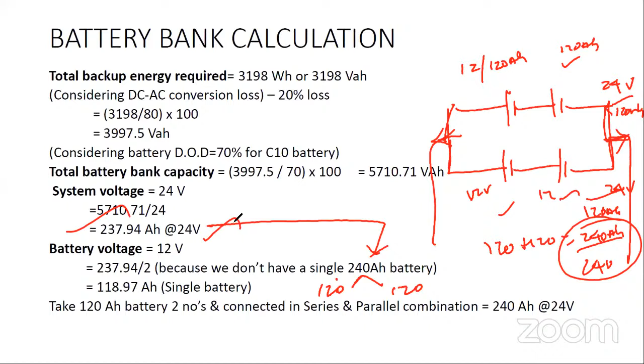So how it has been done now is, each is going to be a 12 volt 120 Ah battery. Now you see 12 in series will give 24 volt. Again 12 in series will give 24 volt. Here, since it is a 120 Ah battery, in series the current remains the same. It is going to be 120 Ah. Same here also, 120 Ah. But again I am paralleling here. Because of the parallel, this 120 plus 120 will become 240 Ah. Already my voltage is 24 volt. So I have achieved the 24 volt 240 Ah requirement. This is how the battery has been designed.